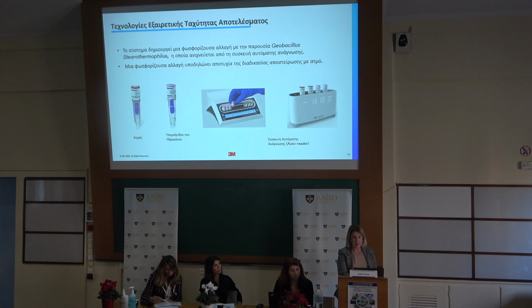In recent years, in fact for more than 10 years now, rapid systems have been in the sterilization units, and they have become super rapid, which means that their response times are reduced. And it has many benefits, of course. In these systems, there is no need to see a color change, because there is a technology: whenever a spore is alive, which means that the sterilization was not able to kill the spore, it will give a fluorescence light and it will be detected by the autoreader. So the autoreader and biological indicators are compact systems which give a result, and when a fluorescent light is detected by the autoreader, it means that there is a failure in the process.